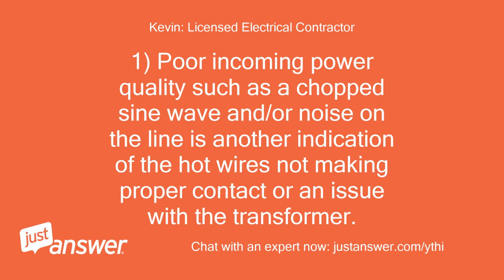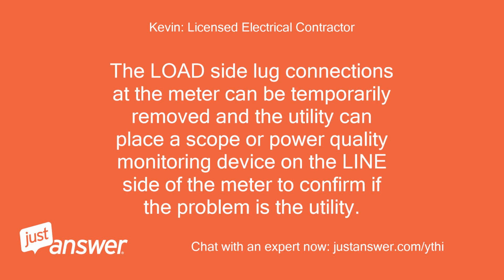1. Poor incoming power quality such as a chopped sine wave and or noise on the line is another indication of the hot wires not making proper contact or an issue with the transformer. The load side lug connections at the meter can be temporarily removed and the utility can place a scope or power quality monitoring device on the line side of the meter to confirm if the problem is the utility.